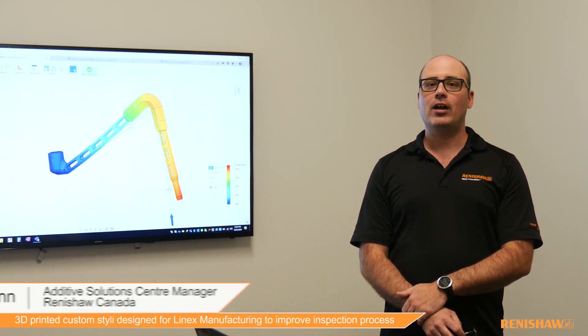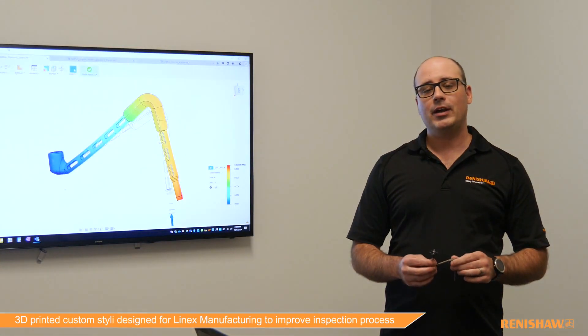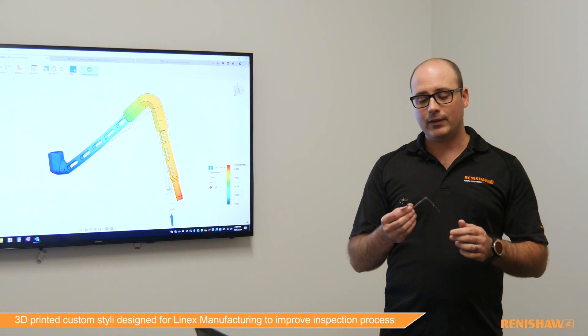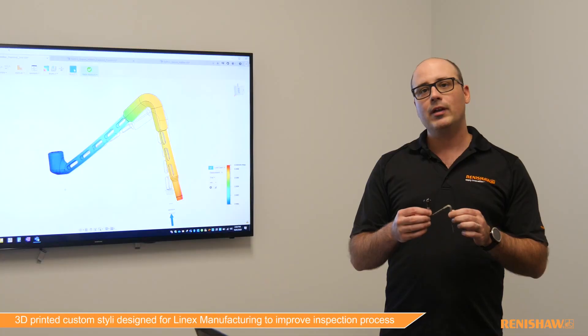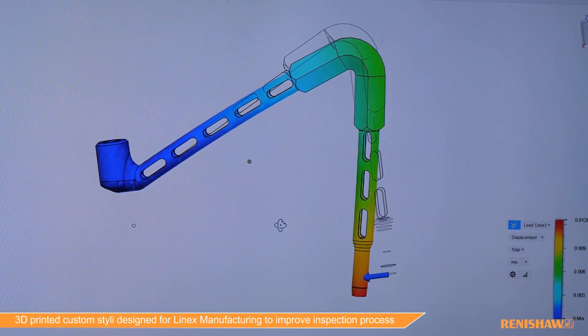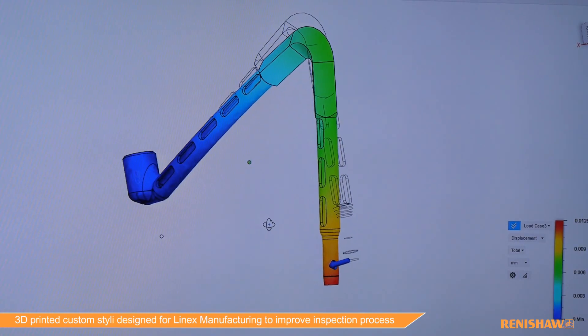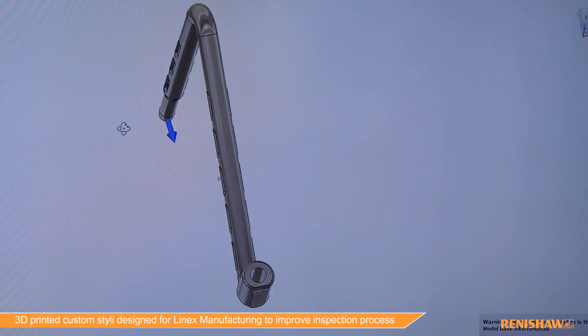It was required to implement a long conventional L-shape assembly styli to be able to reach these holes. When Linex approached us with the challenges they were having with an Equator application and the stylus they were using, we decided to look at additive manufacturing to come up with a monolithic design for the stylus to help improve the measurement quality coming off the Equator. Some of the things we had to look at in that process was we needed to maintain a specific weight for the stylus.